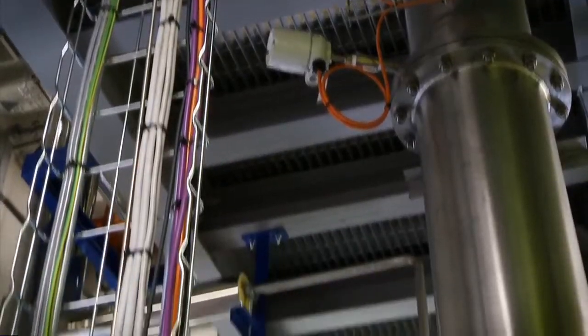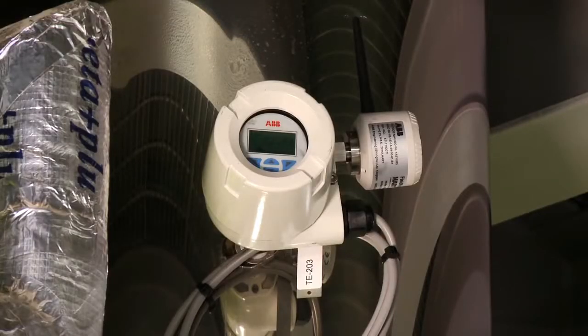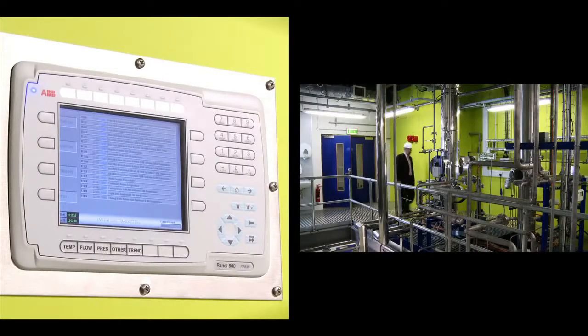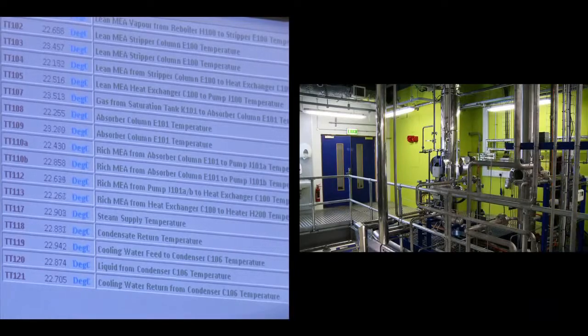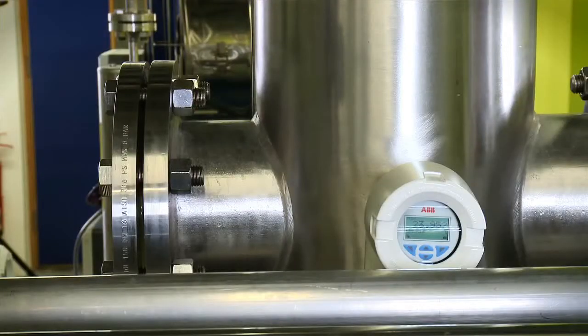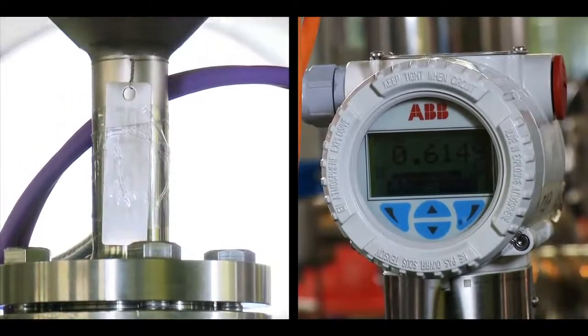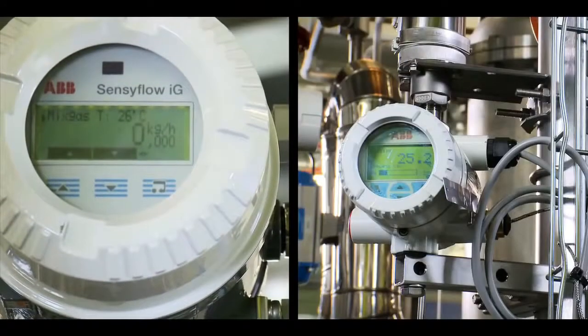Several different communication protocols are used to relate the data from the process instruments including Ethernet, wireless HART and Foundation Fieldbus to the control room. On each floor we also have local HMI or human machine interface control panels. Here we have a cluster of instruments centered around the inspection port on the absorber column. The instruments measure data like flow rates, temperature and pressure, giving detailed feedback on the process to the control system.